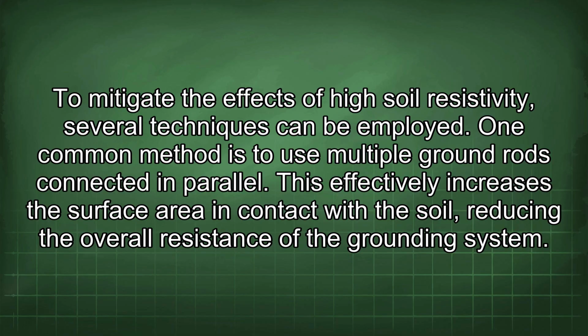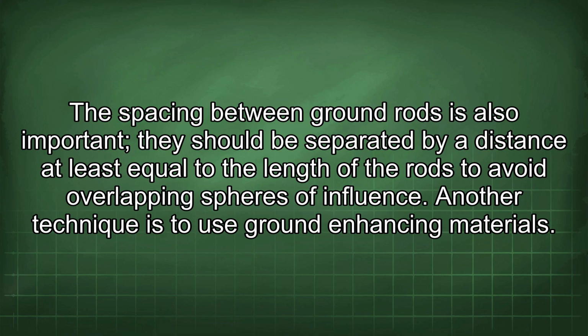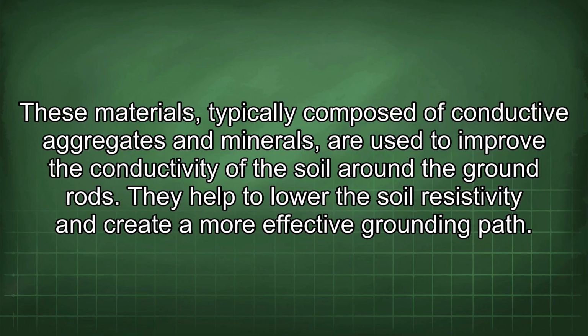One common method is to use multiple ground rods connected in parallel. This effectively increases the surface area in contact with the soil, reducing the overall resistance of the grounding system. The spacing between ground rods is also important. They should be separated by a distance at least equal to the length of the rods to avoid overlapping spheres of influence. Another technique is to use ground-enhancing materials. These materials, typically composed of conductive aggregates and minerals, are used to improve the conductivity of the soil around the ground rods. They help to lower the soil resistivity and create a more effective grounding path.